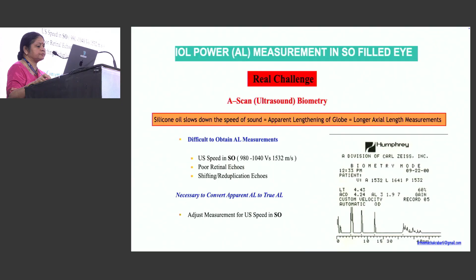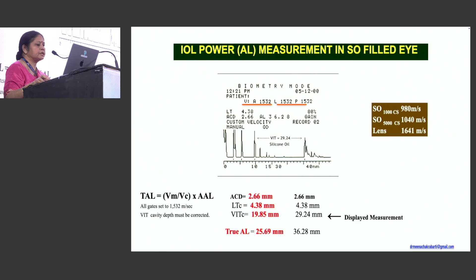If you have an ultrasound biometer which is not very advanced and you cannot set the velocity gate in the vitreous at a particular level, and there is a uniform velocity gate, the axial length you get is much larger than the true axial length. Then in this situation, depending upon the viscosity of the silicone oil that you have implanted in the eye, you can convert it into the true axial length by multiplying it with a conversion factor.